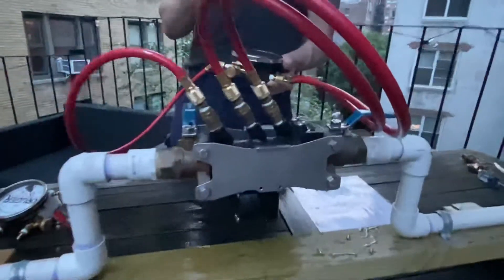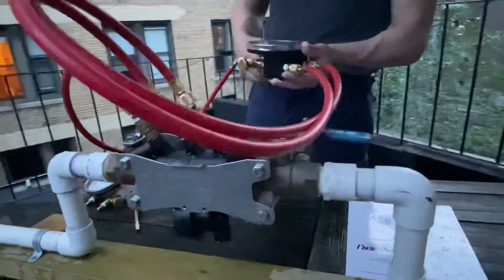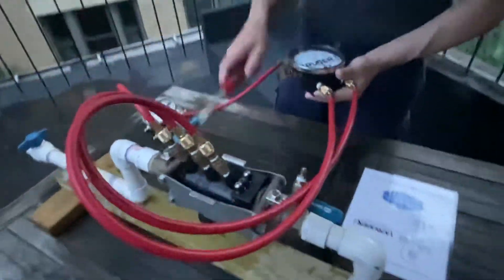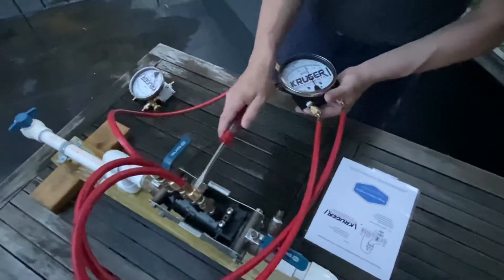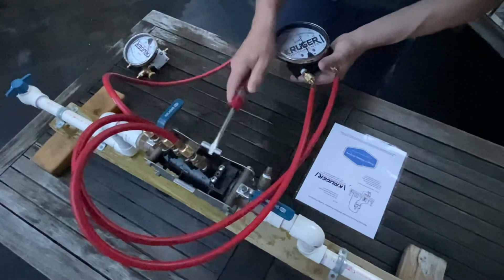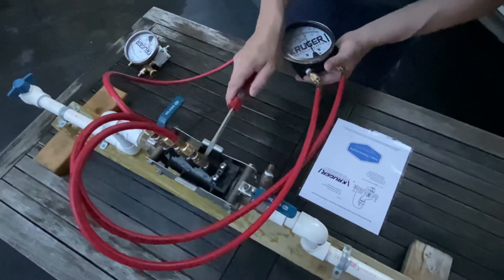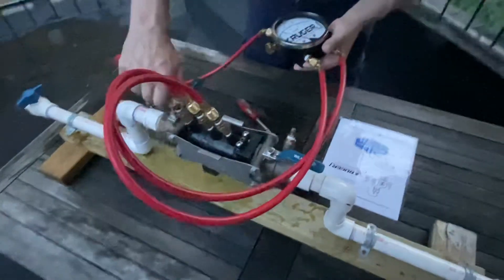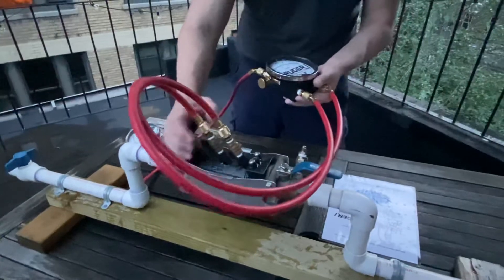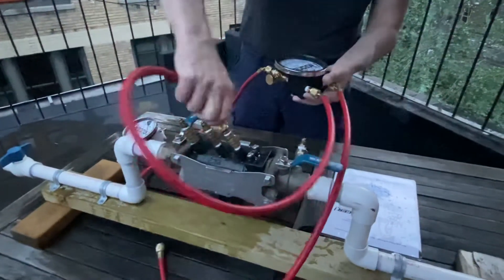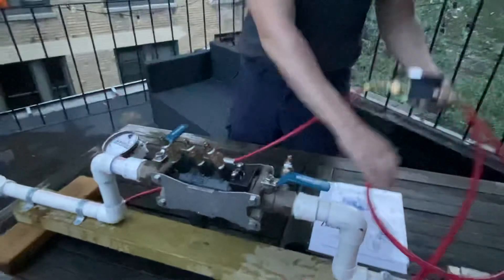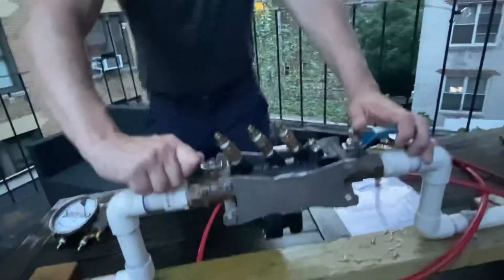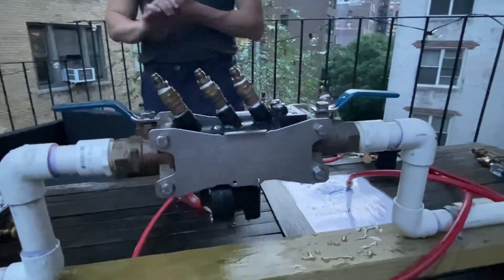So those are the three tests. You got relief valve opening point, check valve two against back pressure, and check valve one differential pressure. So now you're done. Close all test cocks, remove all equipment, and then open shut off valves.